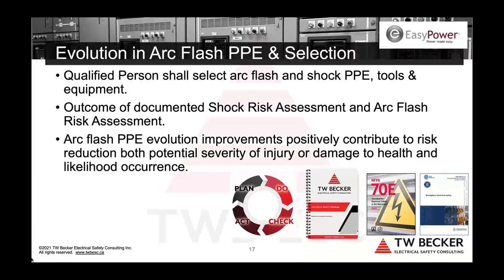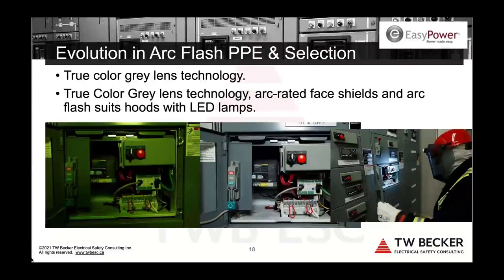So true color gray lens technology, it is unbelievable. And the picture you see on the screen is the green tint on the left, the new true color gray that's available from multiple manufacturers of arc flash suit hoods and arc rated face shields. So night and day, right? Forgive the pun. And then the LED on the right-hand side, they also make it night and day. So it should be mandatory that the employer specifies true color gray lens technology and LED lamps on face shields or hoods. This impacts positively the likelihood of occurrence of the worker making a mistake and creating an abnormal arcing fault and arc flash.